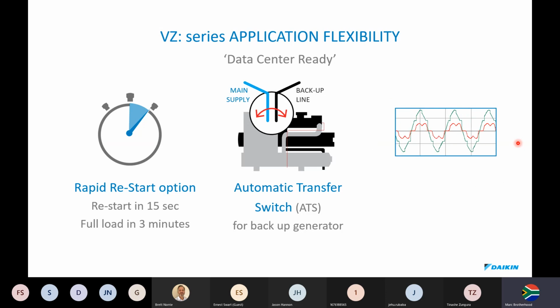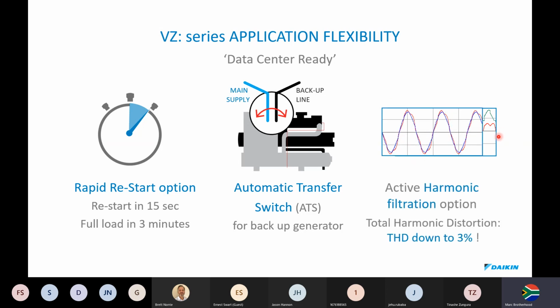If you look at the switch line here, this is the very noisy harmonics that you'll get in data centers because there's so many computers running. They generate a lot of harmonics. What Daikin offer is active harmonic filtration, because the electrical engineer is going to be very critical of the total harmonic distortion that you're feeding back into the power circuit within the data center.